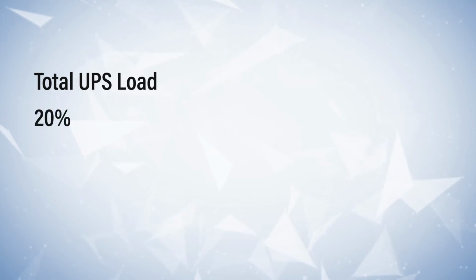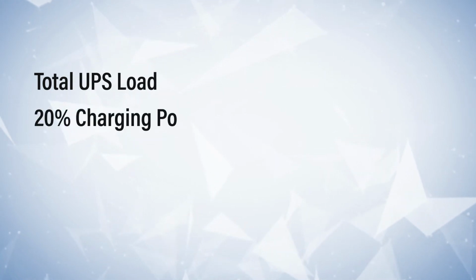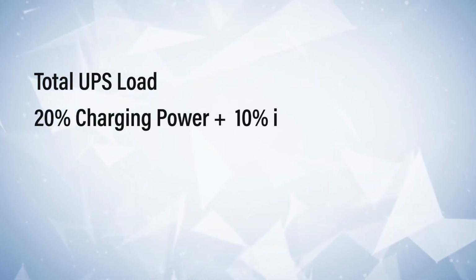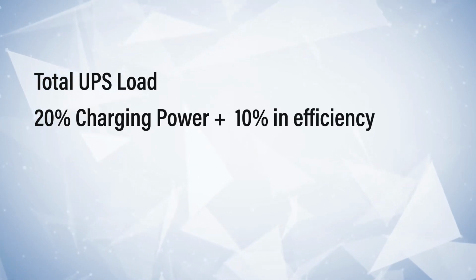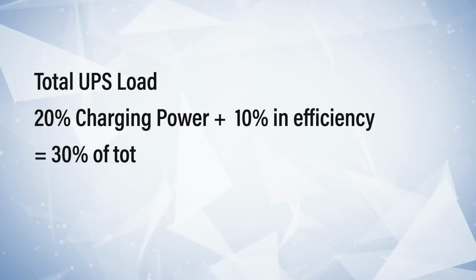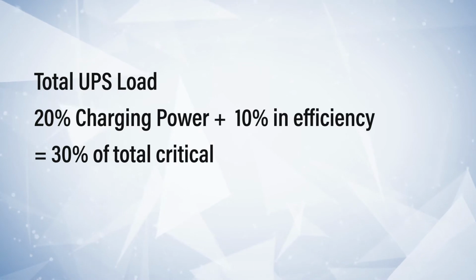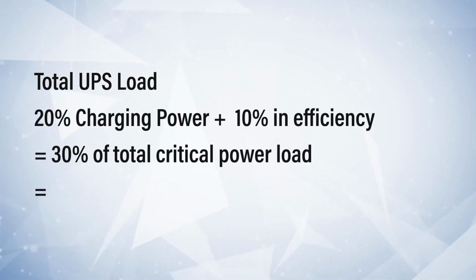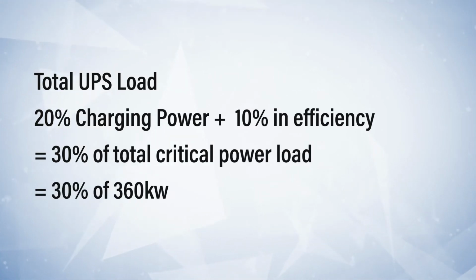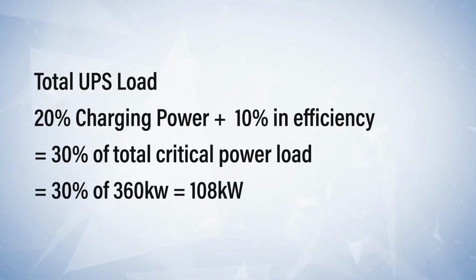Now with 10% UPS inefficiency, and in general a UPS needs 20% power to charge its battery if it is partially or completely discharged. So summing these two gives the power load required for the UPS, which is 30% of critical load, which is 360 kilowatt. So the 30% of 360 kilowatt is 108 kilowatt. This is your total UPS load.